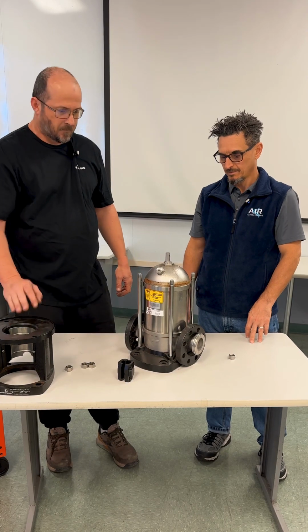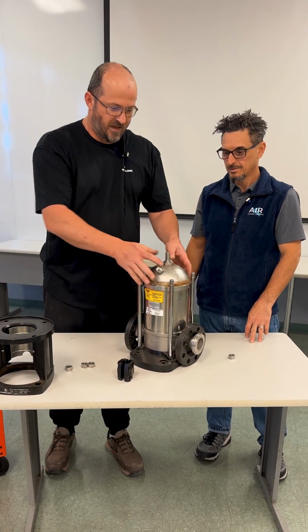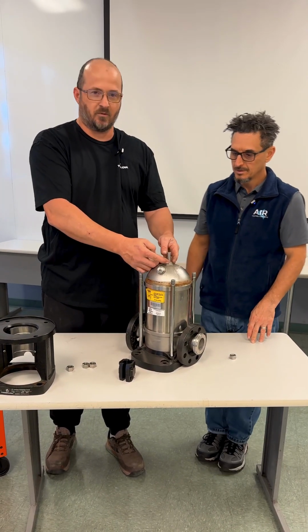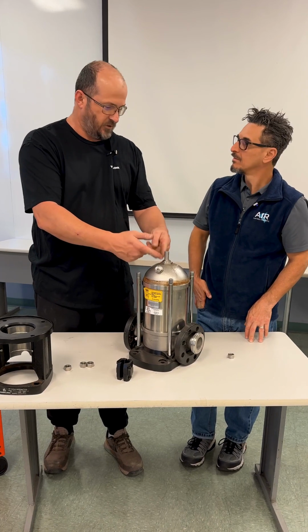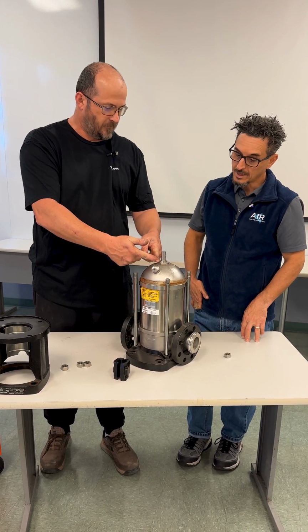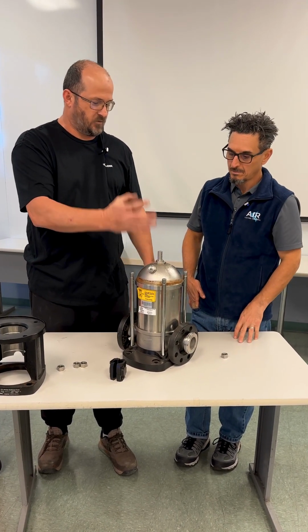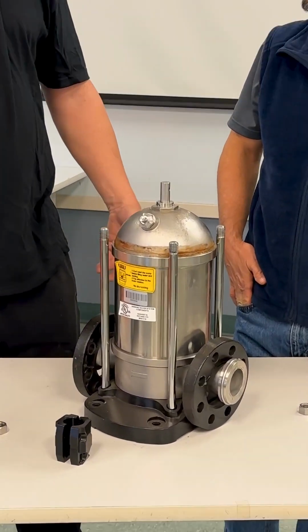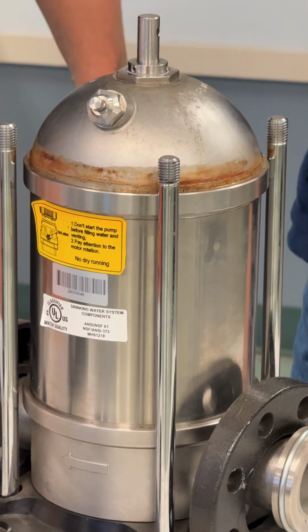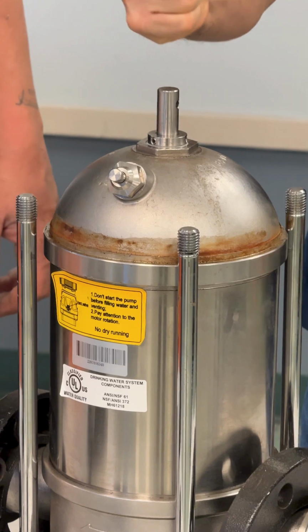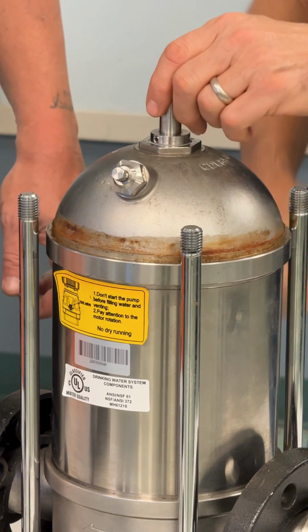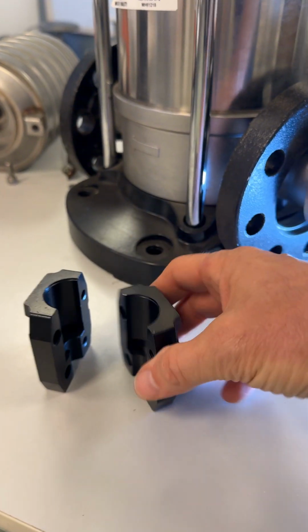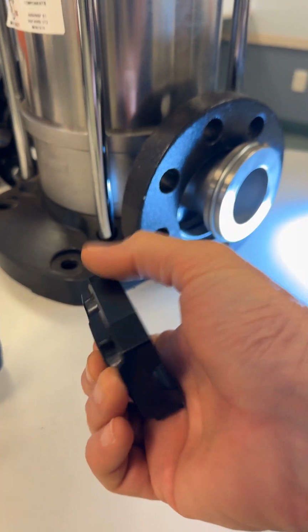Correct. Got it. Next step, if everything was tight, you would loosen up the 3 set screws on your mechanical seal, which is this component right here. That's the seal right there? That's the seal right there. That's what keeps the water inside the pump instead of spraying out everywhere, because the pump has a shaft on it that spins, and then there's a coupler that connects the two. Yes, this right here spins the impellers, which we're going to look at in a minute. Okay, gotcha, correct.